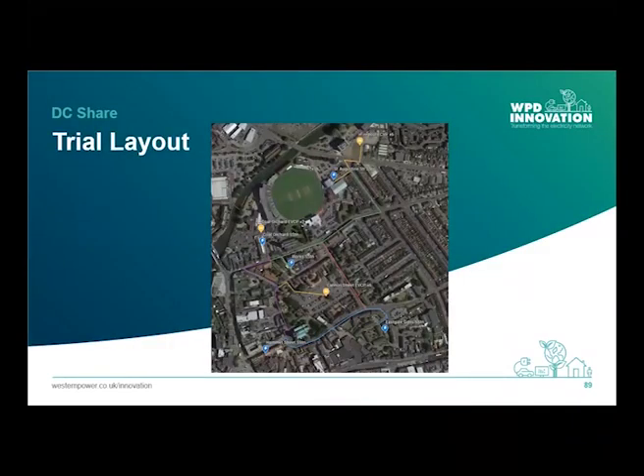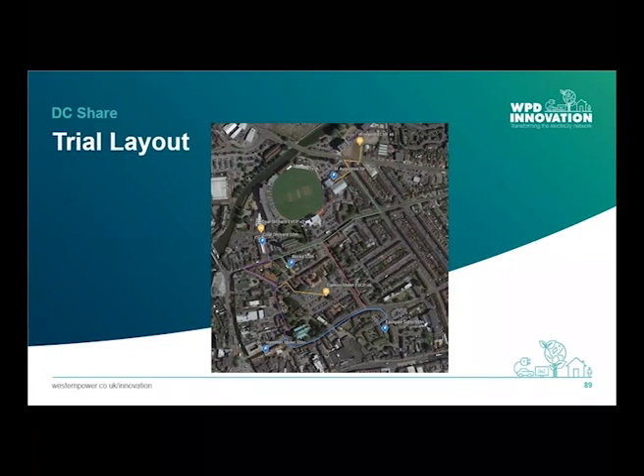This is what the trial network will look like in Taunton. We're going to place rapid chargers in Firepool Car Park, where there'll be six, Cannon Street Car Park, where we'll deploy another six, and Coal Orchard Car Park, where we'll deploy three. These will be a mix of 100 kilowatt CCS chargers and 50 kilowatt CHAdeMO chargers. The four substations supplying the network are St Augustine Street, the Works Substation, Eastgate Gardens and Hammett Street, all housing the grid-tied inverters which take the latent AC capacity and convert it into DC. In the Coal Orchard substation, we're also putting a control point for the control system, which will look after all the EV chargers and GTIs and keep everything talking to each other and responding in real time.